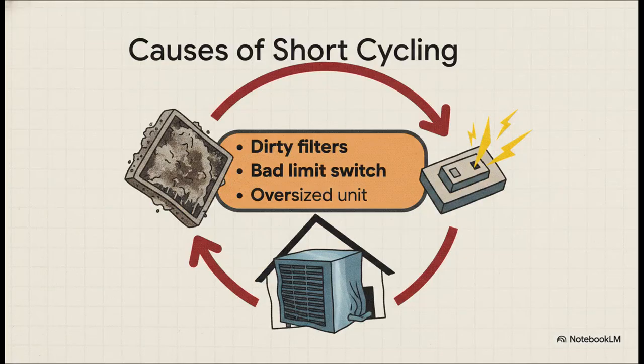Now, the culprits behind this range from super simple fixes to some pretty major design flaws. The most common one, a dirty filter restricting your airflow. It causes the system to overheat and triggers a safety shutoff. It could also be a failed limit switch, maybe a malfunctioning thermostat, or, like we mentioned, leaky ductwork dumping heat into the attic and throwing off the temperature readings. But another massive issue is oversized equipment. If your system is too big for your house, it heats or cools the space way too fast and then just shuts off abruptly. So yeah, bigger is definitely not always better in the HVAC world.